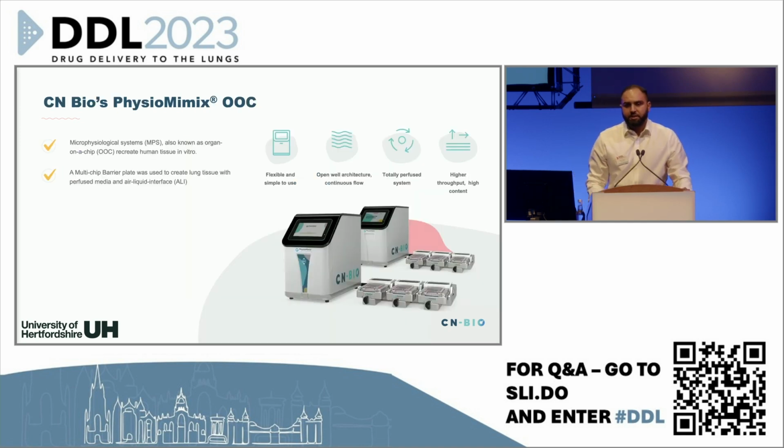The microphysiological system that I utilized in my project was the PhysioMimix system developed by CN Bio Innovations. This system is a totally perfused system using an open well format. The system itself uses a docking station and drivers that sit within the incubator, and then a plate where the cells are cultured, and a controller that sits outside of the incubator for control over the flow, which is completely tunable.